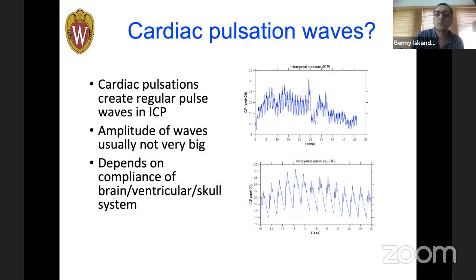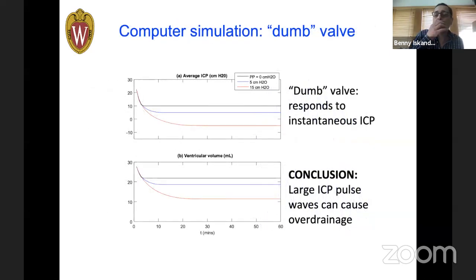So this is what cardiac pulsation waves look like. This is what an existing valve looks like. So for example, let's say an existing valve is supposed to maintain an ICP of 10 in the brain. Because of the instantaneous pulses, the ICP keeps creeping below that average, so that it ends up being -5 instead of being 10.